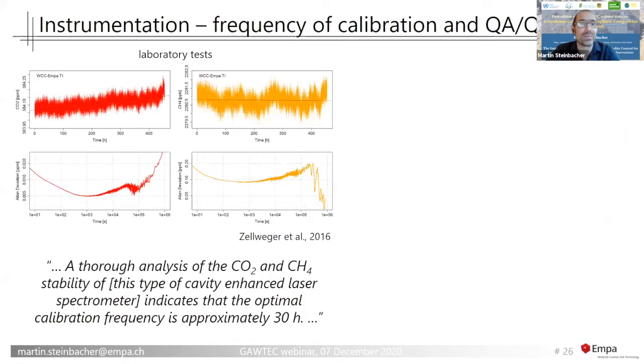But then we are here. How often do you want to calibrate? For the newest generation of high precision analyzers that are usually also very fast, it is common to do Allan variance tests. You just measure one tank for, in this case, more than 400 hours, let's say 10 days.